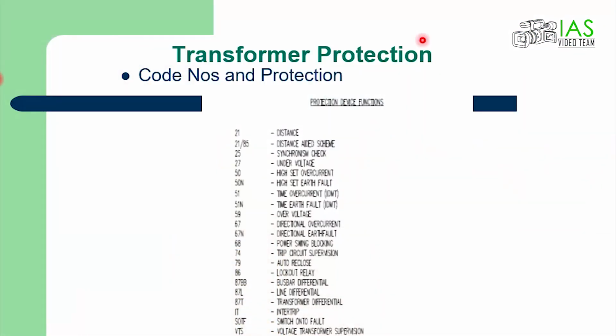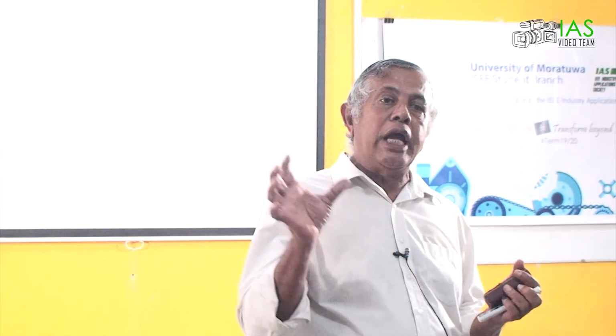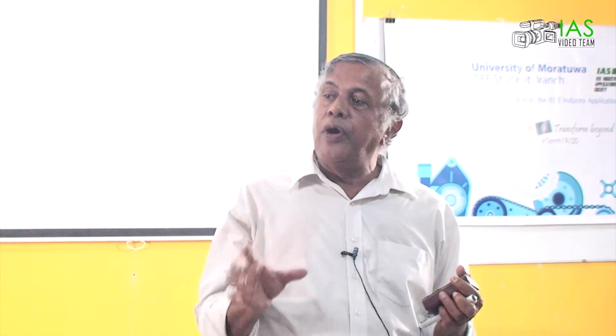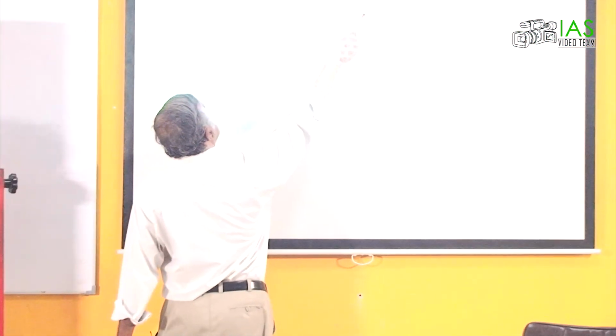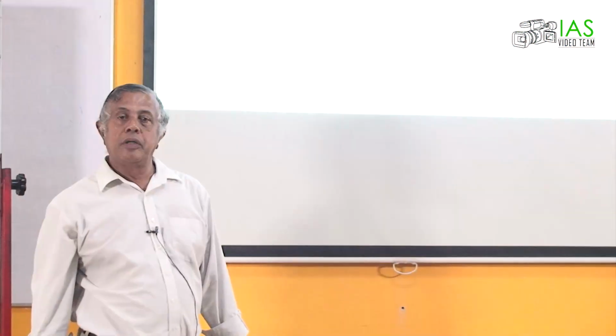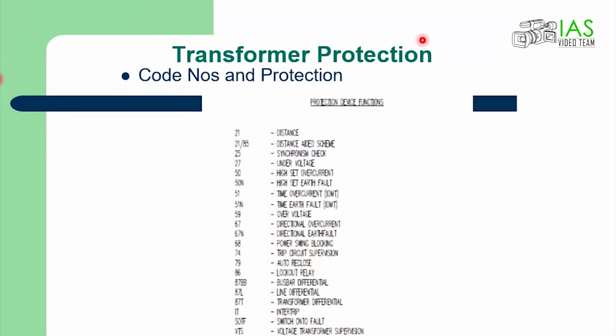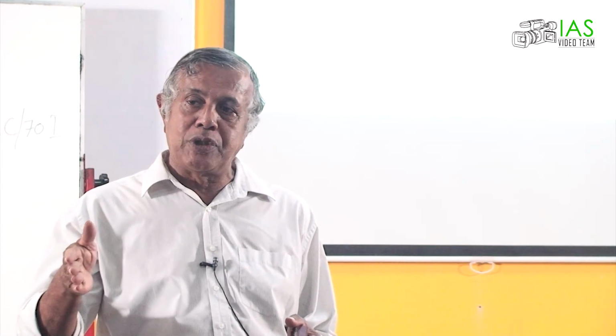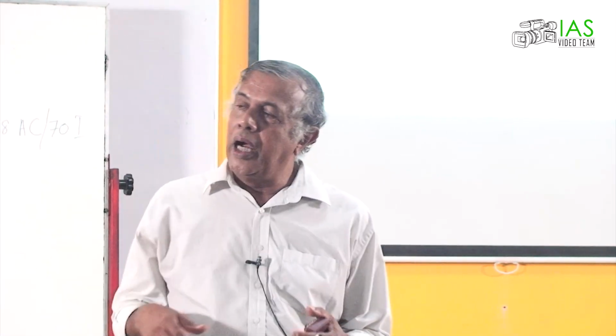Now these numbers, 21 and 58, okay, 50 and whatever, are the assigned identification numbers for each protection function. Like this, 50 is high set overcurrent. So 50N is the high set earth fault. High set means if you reach that current, it switches off, okay, trips immediately, right? That is a high set.